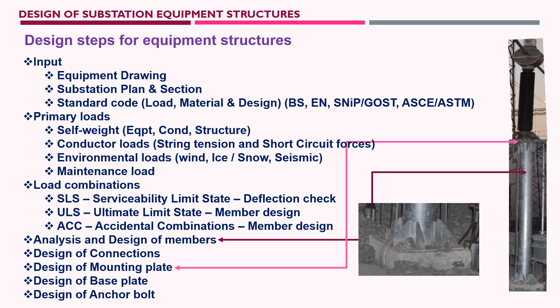Next is the mounting plate — shown in pink at the top of the structure — where the equipment is mounted. The mounting plate thickness and required stiffener plates must be designed. If the cantilever projection distance of the mounting plate is large, additional stiffener plates are needed. The weld connection of the mounting plate must also be designed.